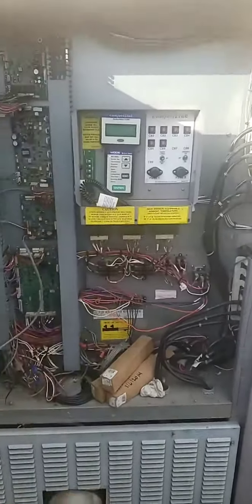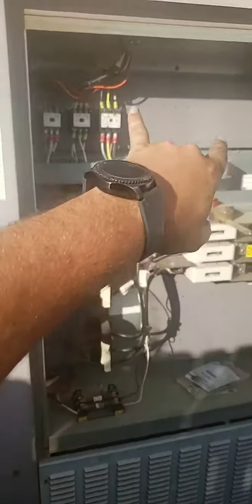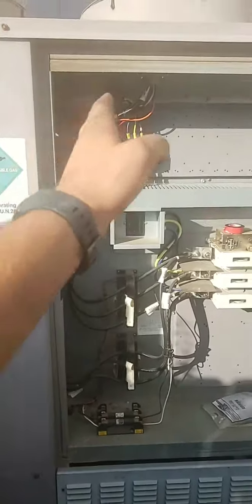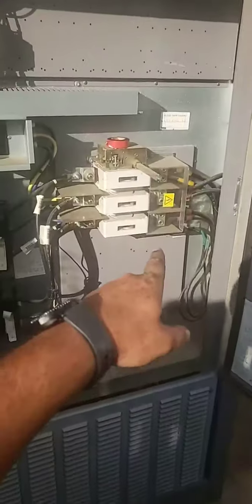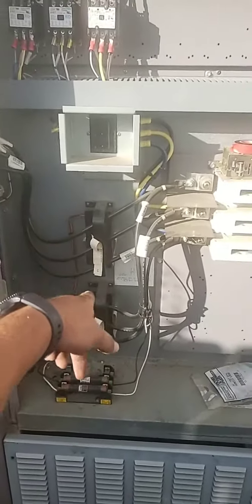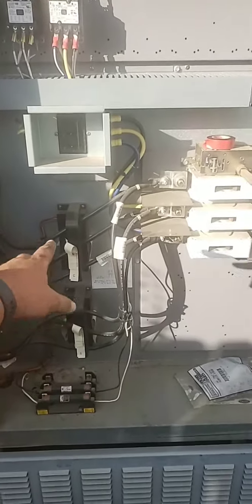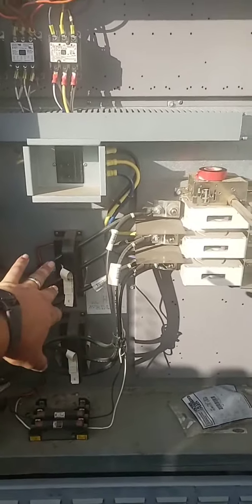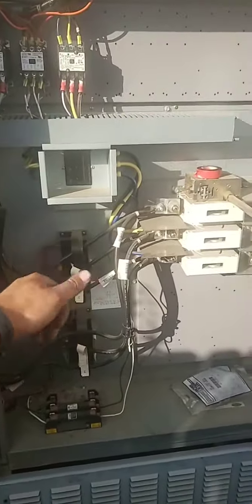Anyway, this is your controls compartment. This is your power compartment. These are your condenser fans. Those condenser fans stage, so you have 6 fans total. They stage 1, 2, and 3 in staging, and it stages them off of the condenser saturation. Again, this is 134A. Every time you hit about 110 degrees of saturation, it's going to stage up until it stages to maximum all the way. That's your main power coming in. These are your CTs monitoring or your overloads. That's your system overload. So if it sees any kind of too much phase imbalance, or just high amperage, anything to do with the amperage or incoming power, it's going to catch it there and trip it out.